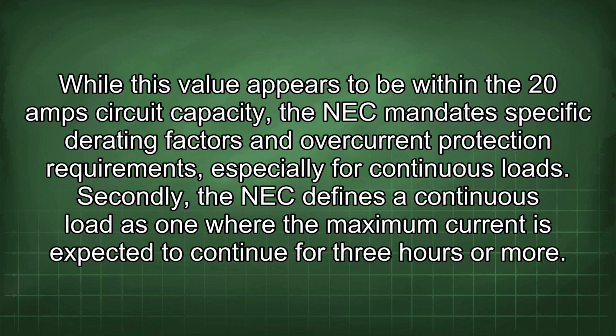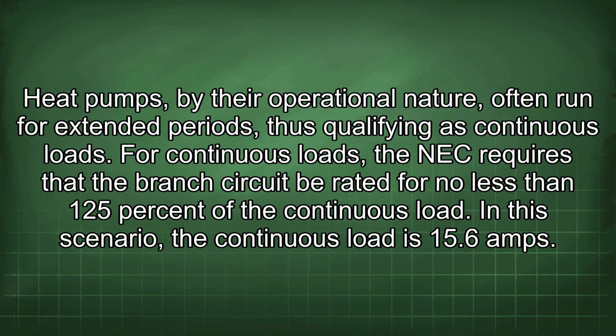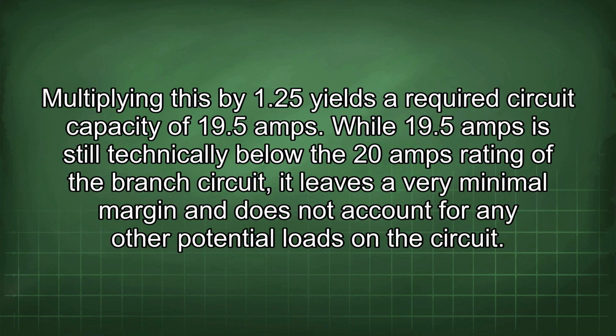Secondly, the NEC defines a continuous load as one where the maximum current is expected to continue for 3 hours or more. Heat pumps, by their operational nature, often run for extended periods, thus qualifying as continuous loads. For continuous loads, the NEC requires that the branch circuit be rated for no less than 125% of the continuous load. In this scenario, the continuous load is 15.6 amps. Multiplying this by 1.25 yields a required circuit capacity of 19.5 amps. While 19.5 amps is still technically below the 20 amps rating of the branch circuit, it leaves a very minimal margin and does not account for any other potential loads on the circuit.